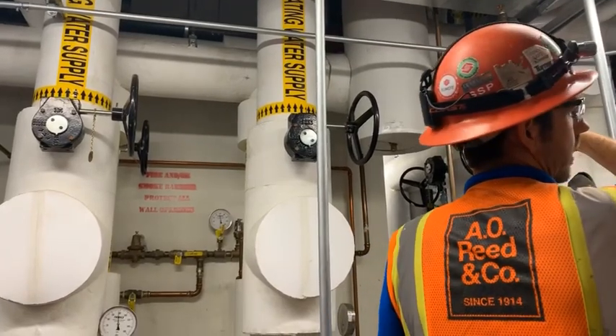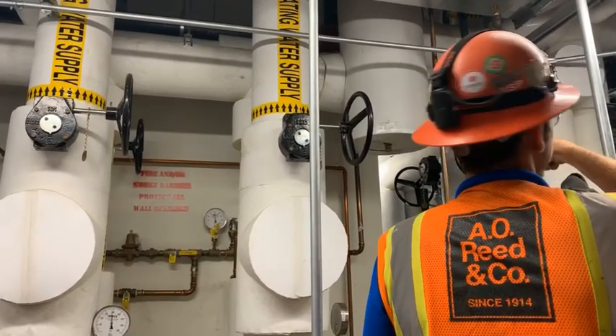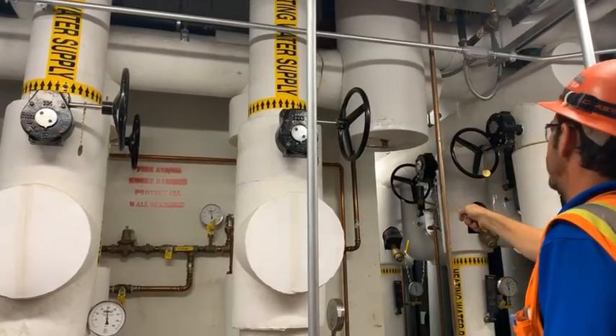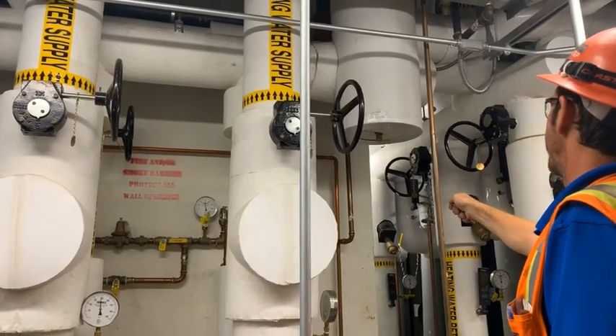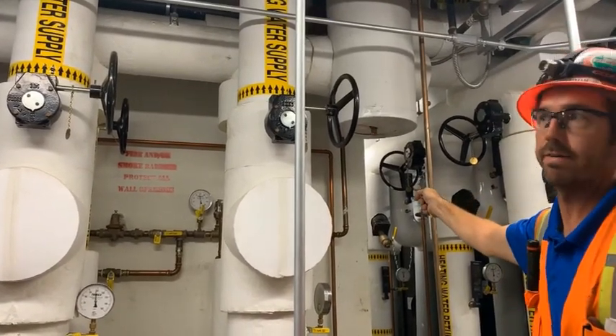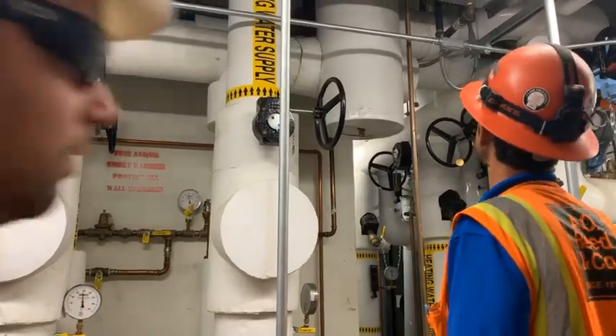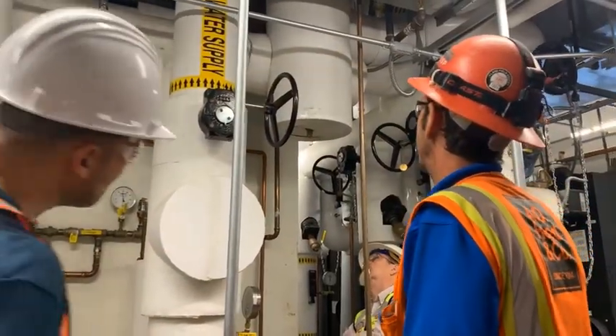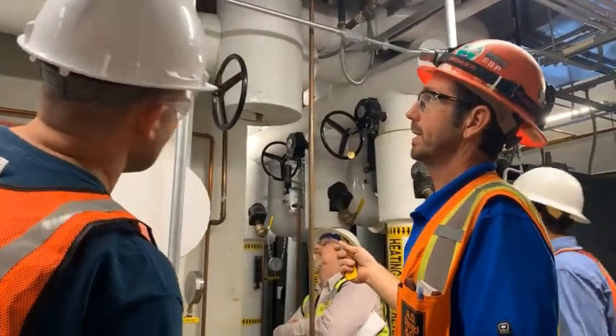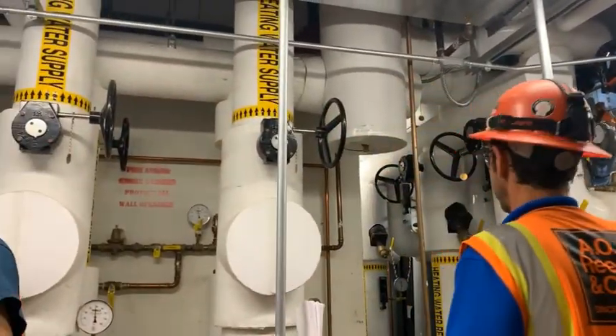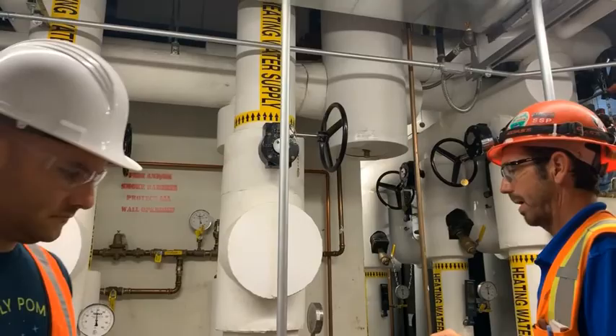Everybody familiar with the air separator? There is a blow down drain here at the bottom. There is a cutout here that you can reach the handle, okay? There's a shutoff valve handle up inside this thing. I'd probably blow that thing down once a year. There are blowdowns at the bottom of each pump too.